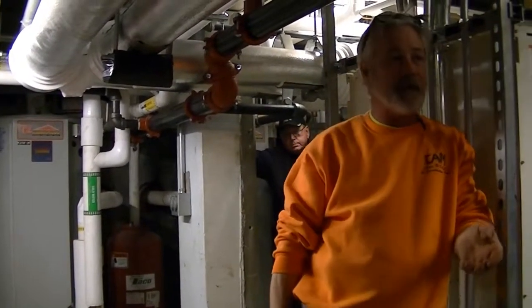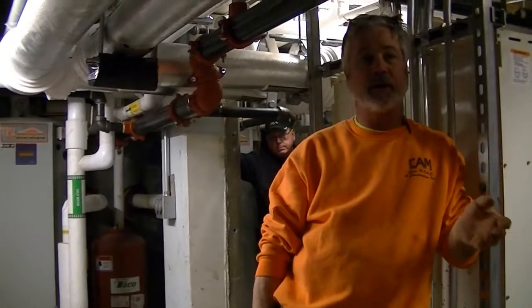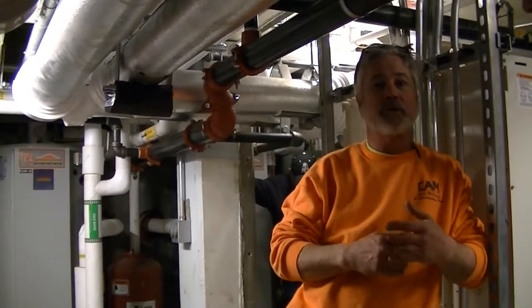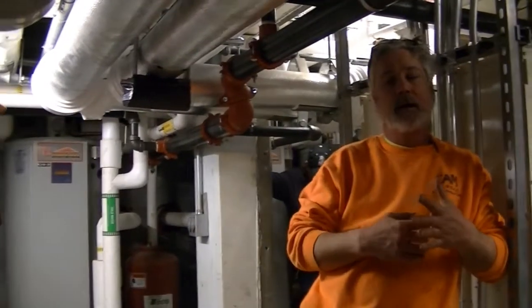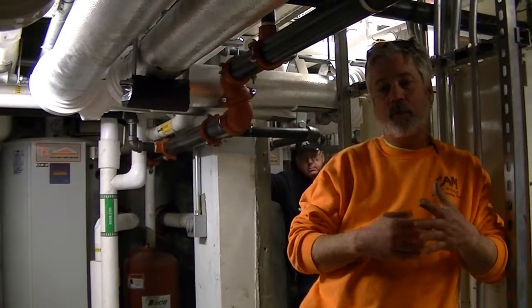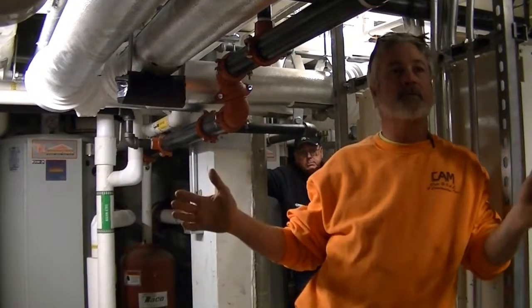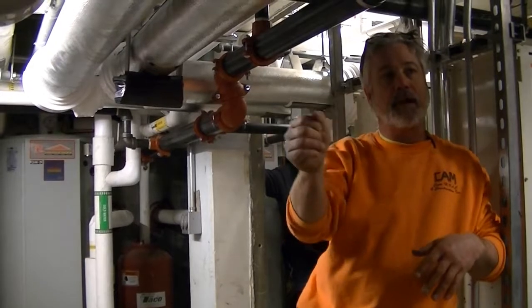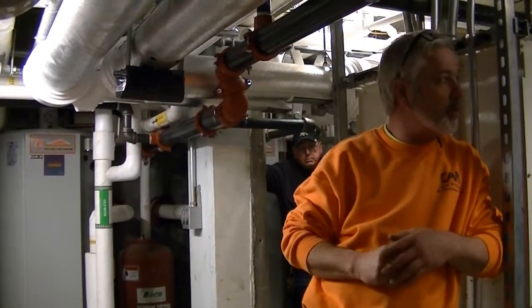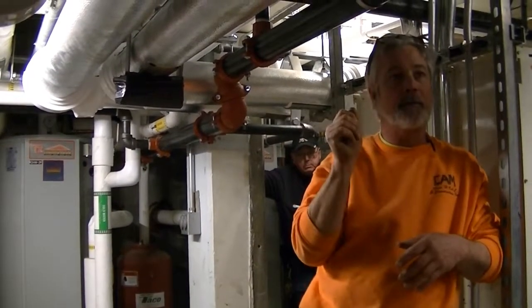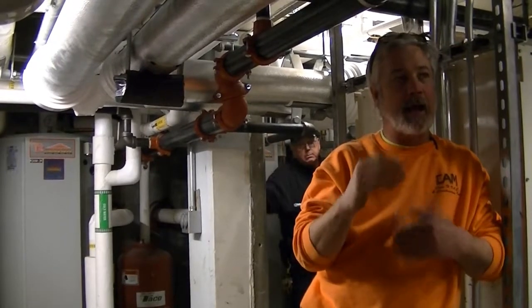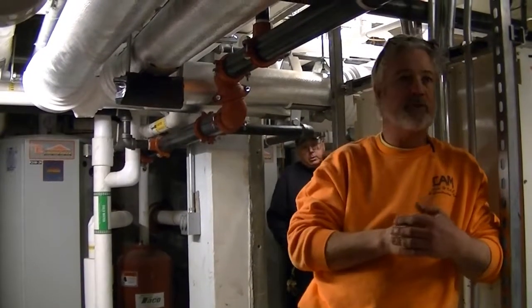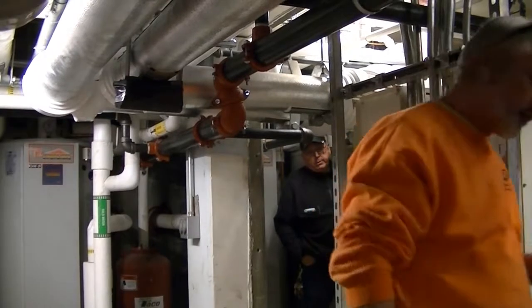That'd be something you'd have to have your in-house heating guy make sure he sets up correctly. When you look at the Viessmann wiring schematic, it'll give you the plug connector that goes to that three-way valve control. You basically just unplug it, take that relay card out of service, and then come over to the actuators. Come over, I'll show you where that is.